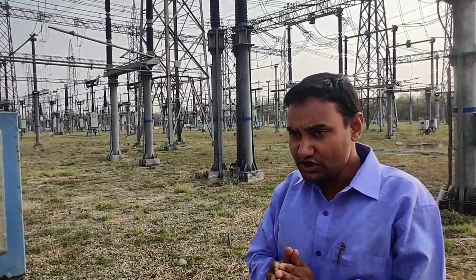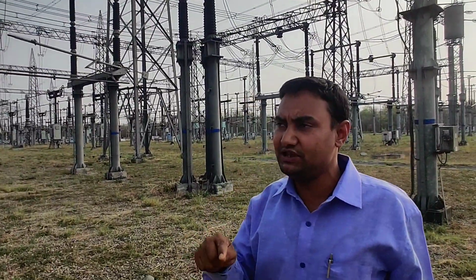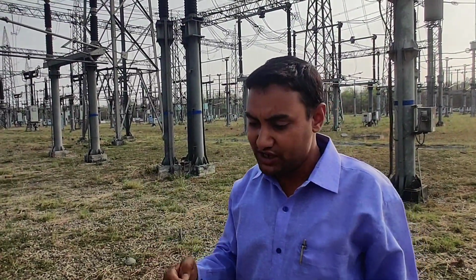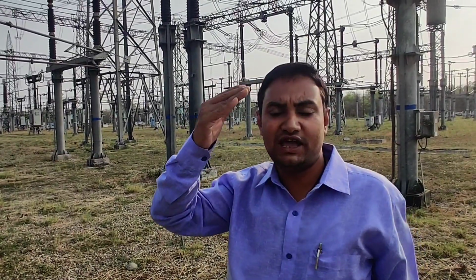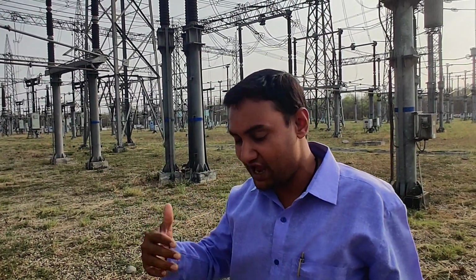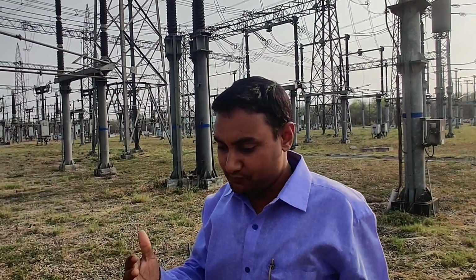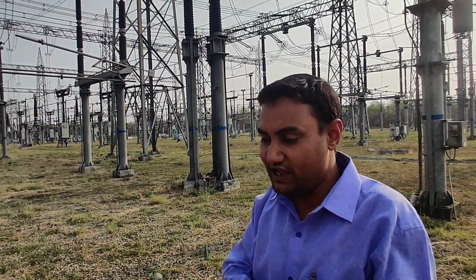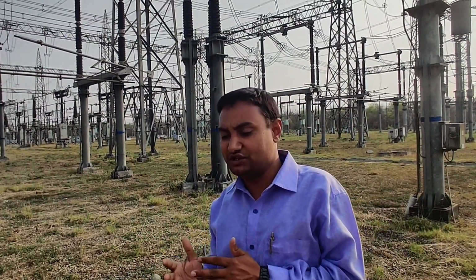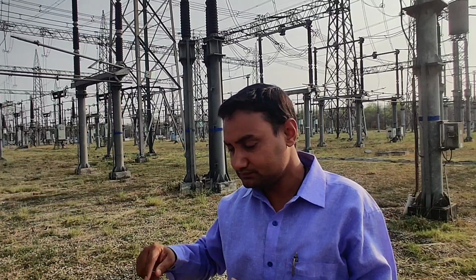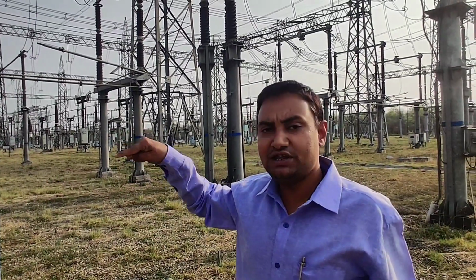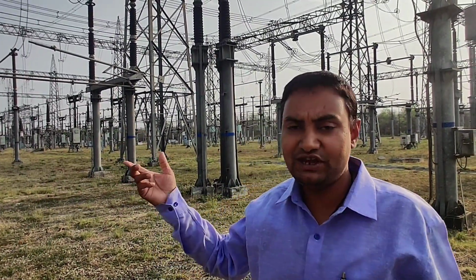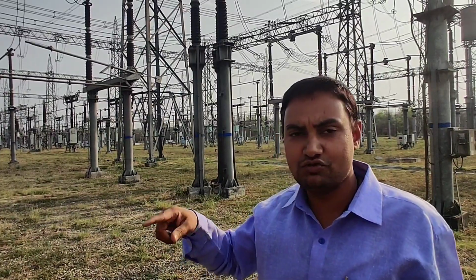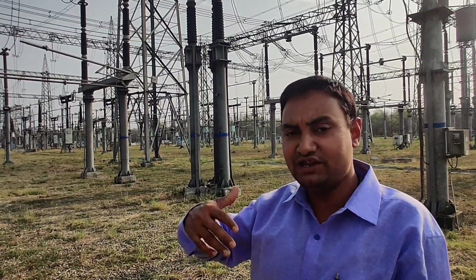So you know that PLCC is basically power line carrier communication. That means over this transmission line we are using a high frequency carrier signal for protection of the transmission line. For this high frequency carrier signal, the capacitive reactance is Xc equals 1 by 2 pi f c. So the higher the frequency, the lower will be the impedance.